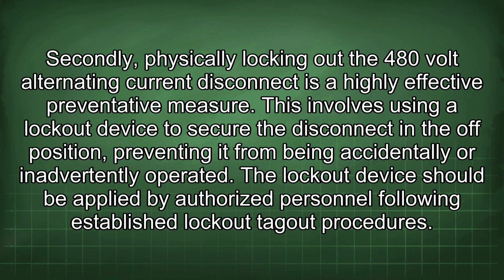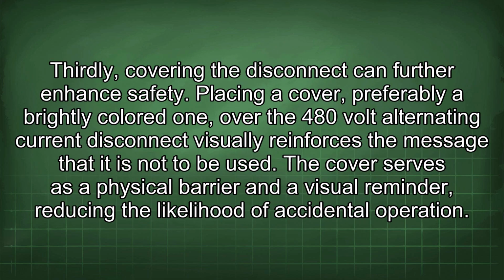Secondly, physically locking out the 480-volt alternating current disconnect is a highly effective preventative measure. This involves using a lockout device to secure the disconnect in the off position, preventing it from being accidentally or inadvertently operated. The lockout device should be applied by authorized personnel following established lockout-tagout procedures. Thirdly, covering the disconnect can further enhance safety. Placing a cover, preferably a brightly colored one, over the 480-volt alternating current disconnect visually reinforces the message that it is not to be used. The cover serves as a physical barrier and a visual reminder, reducing the likelihood of accidental operation.